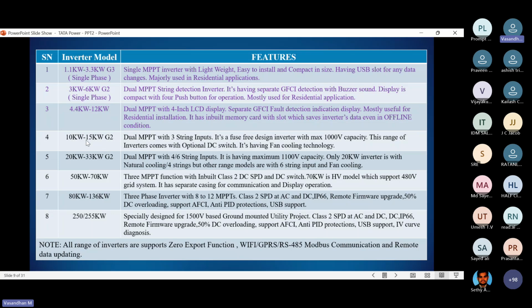Next, the 10 kilowatt to 15 kilowatt G2 model, dual MPPT with 3 string inputs, maximum 1000 volt capacity. And 20 to 33 kilowatt dual MPPT, 4 and 6 string inputs and 1100 volt capacity. Only the 20 kilowatt inverter has natural cooling, for 4 strings. And next, 50 to 70, these have the MPPT function inbuilt. 2 DC SPD switches are available.